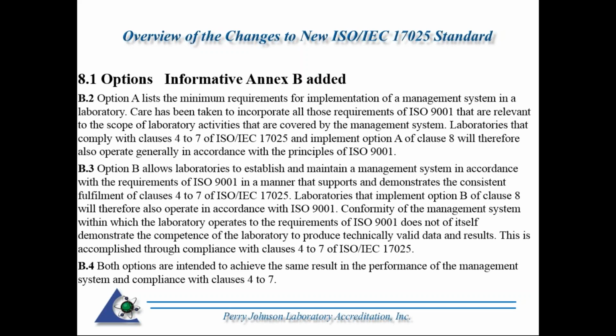Laboratories that comply with Sections 4 to 7 of ISO 17025 and implement Option A of Clause 8 will therefore also operate generally in accordance with the principles of 9001. So with Option A, all those elements, and we'll see exactly what they are again on the next slide, would be subject to the assessment. And they were written to align with those requirements within 9001.